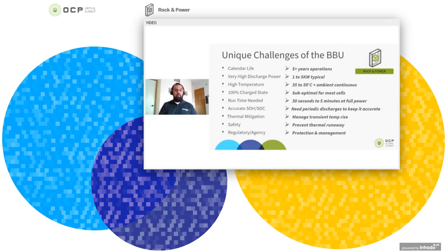Most critical is the cell. Most lithium cells are spec'd to a max of 80 Celsius for skin temperature, including overshoot. And if you start at an ambient of 50 Celsius, you only have a 30 C margin, which is not very big considering the amount of discharge power that's coming from the BBU. So we need to look at component selection, mechanical design, and software design to actually manage the heat.